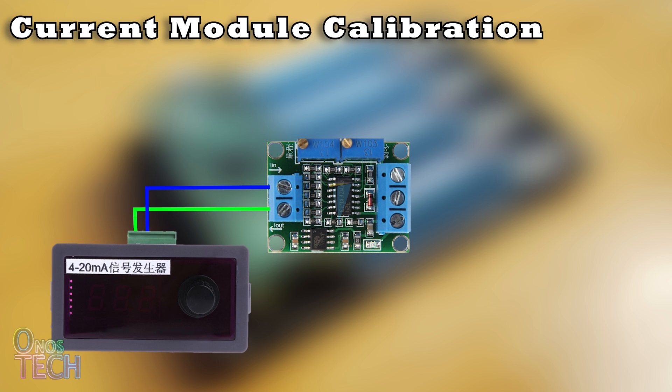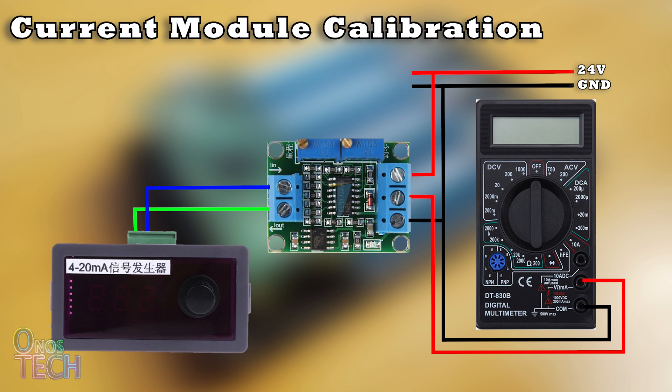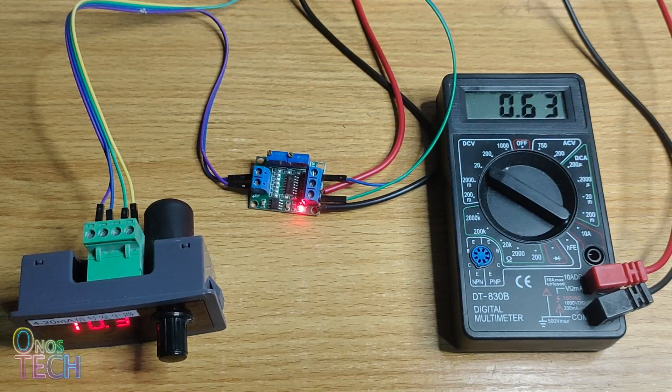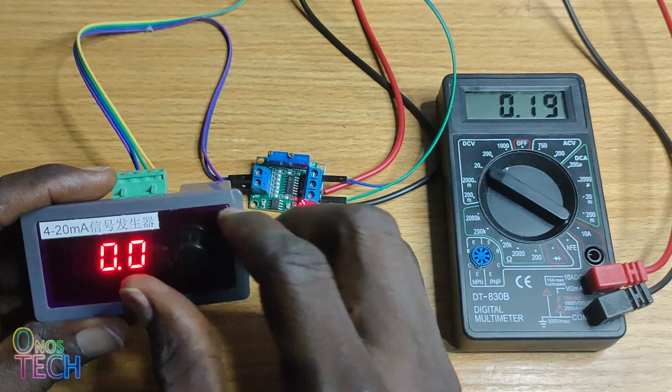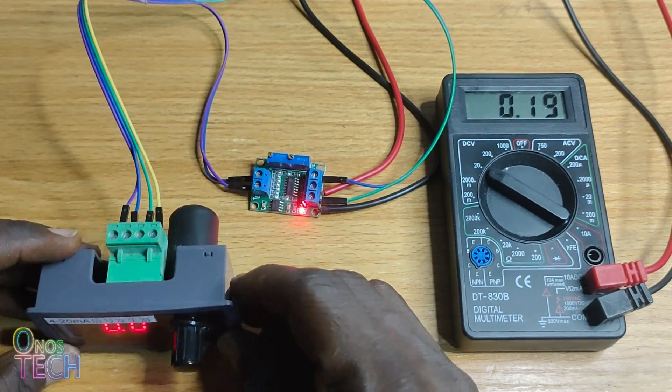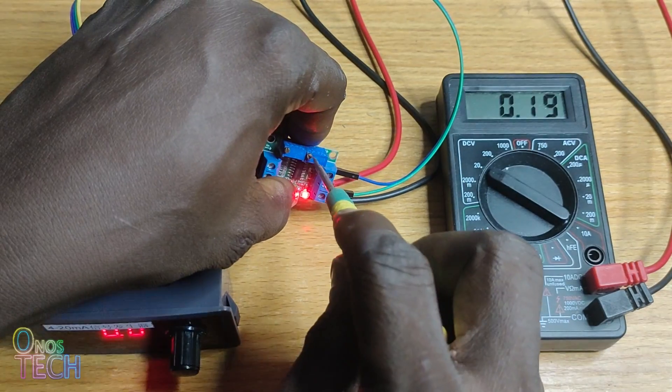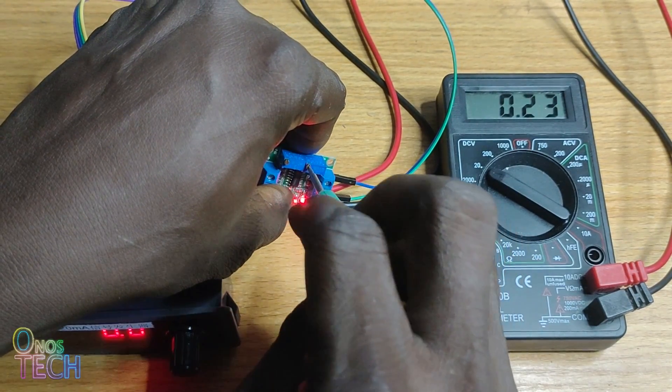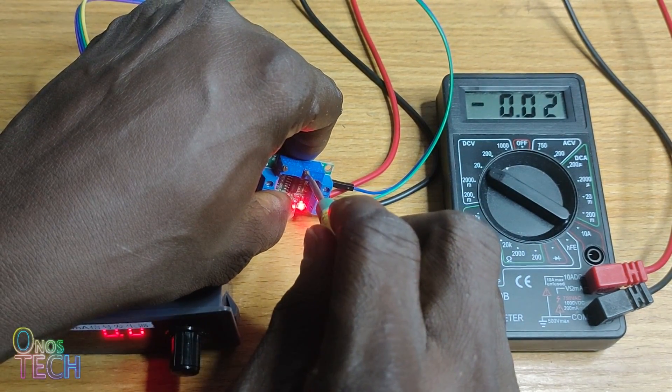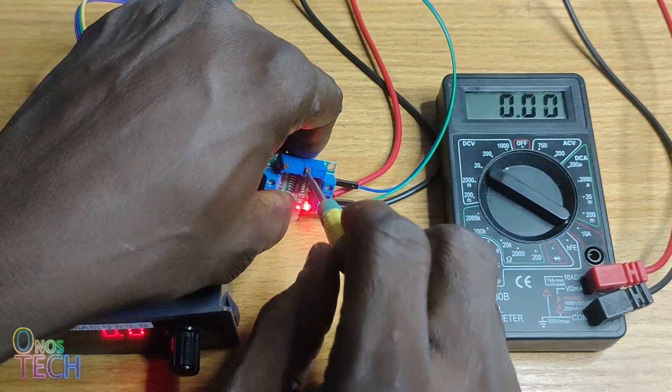Set up the connection to calibrate the module with a 4 to 20mA current source and a multimeter to measure the voltage. Set the current source to 0%. Adjust the right potentiometer on the module with a small screwdriver until the multimeter reading is zero.